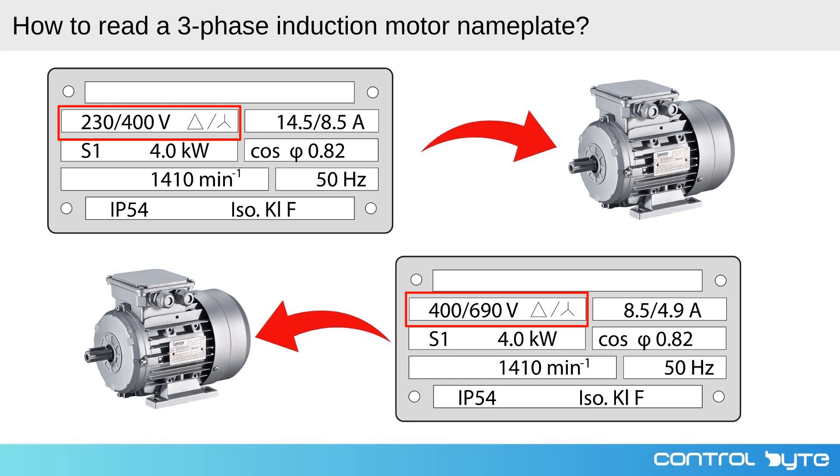The first number refers to the voltage if the motor is connected in a delta configuration, and the second number refers to the voltage if it is connected in a star configuration. It's important to match the motor's voltage rating with the supply voltage to ensure efficient operation and to avoid damaging the motor.